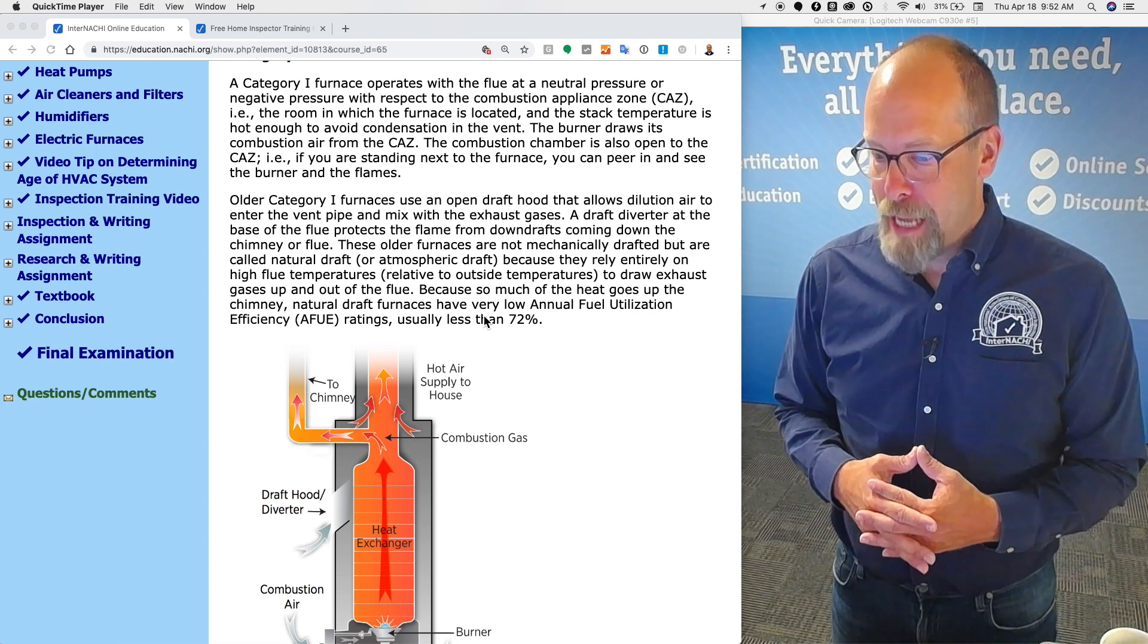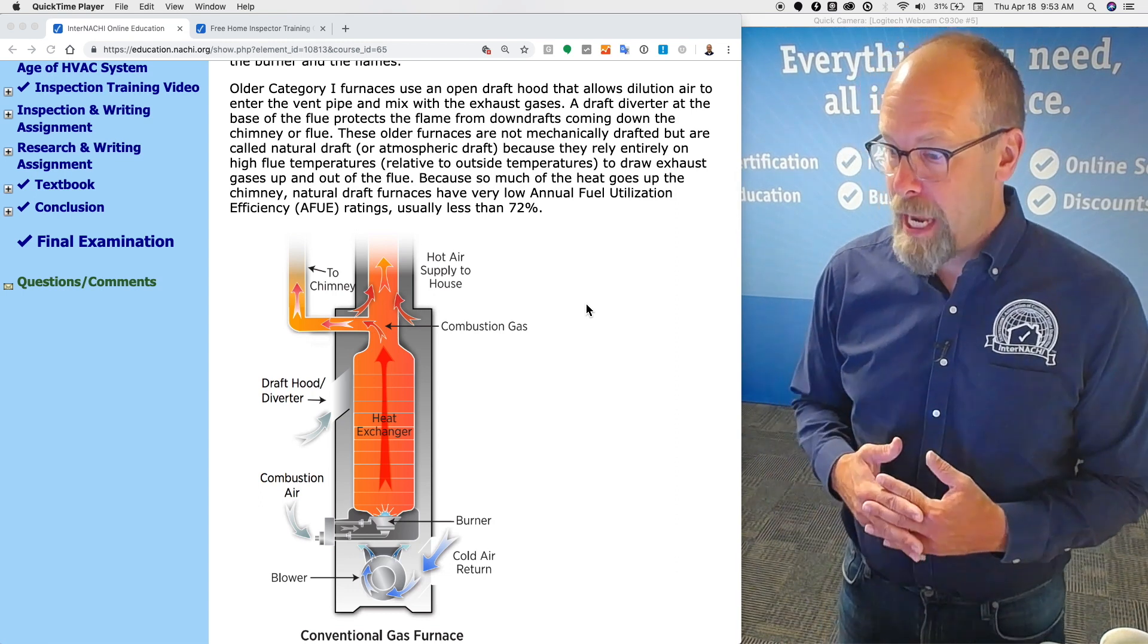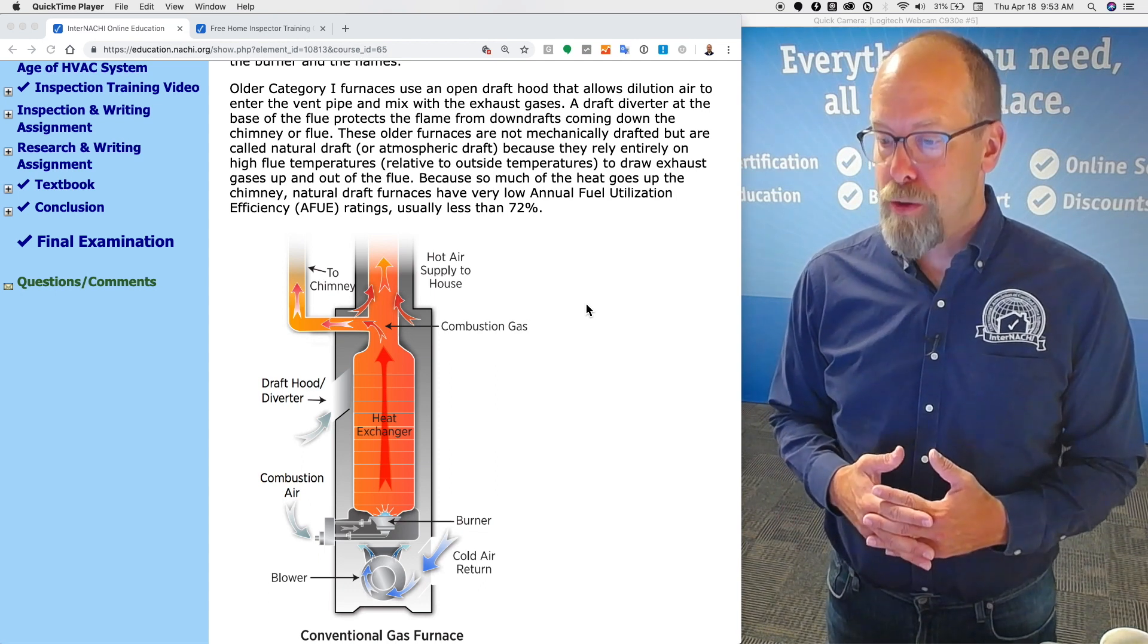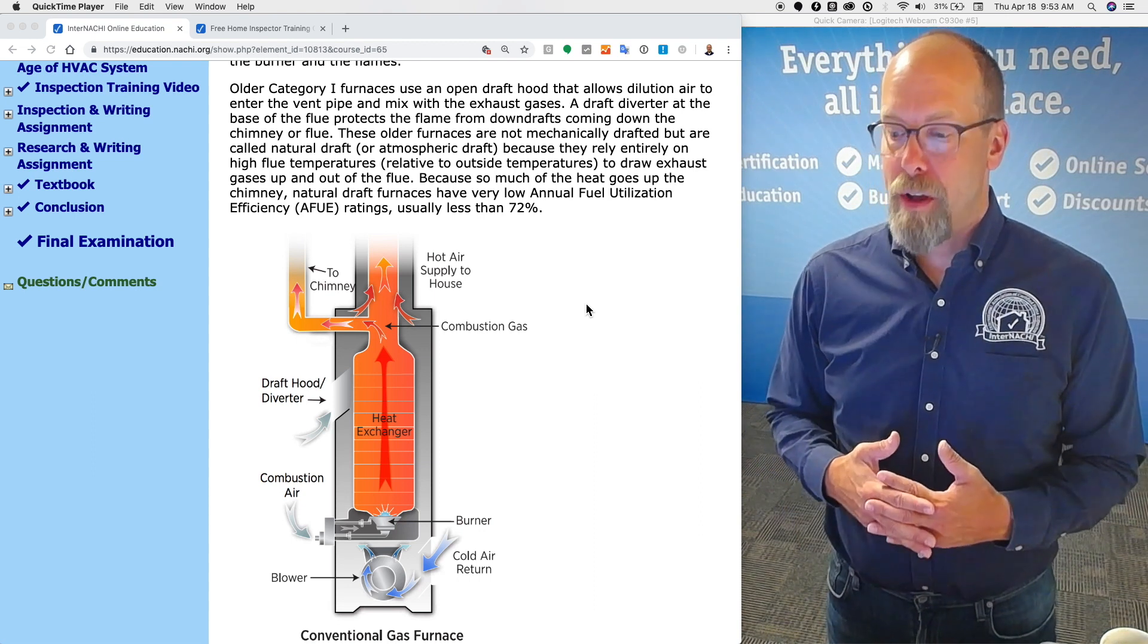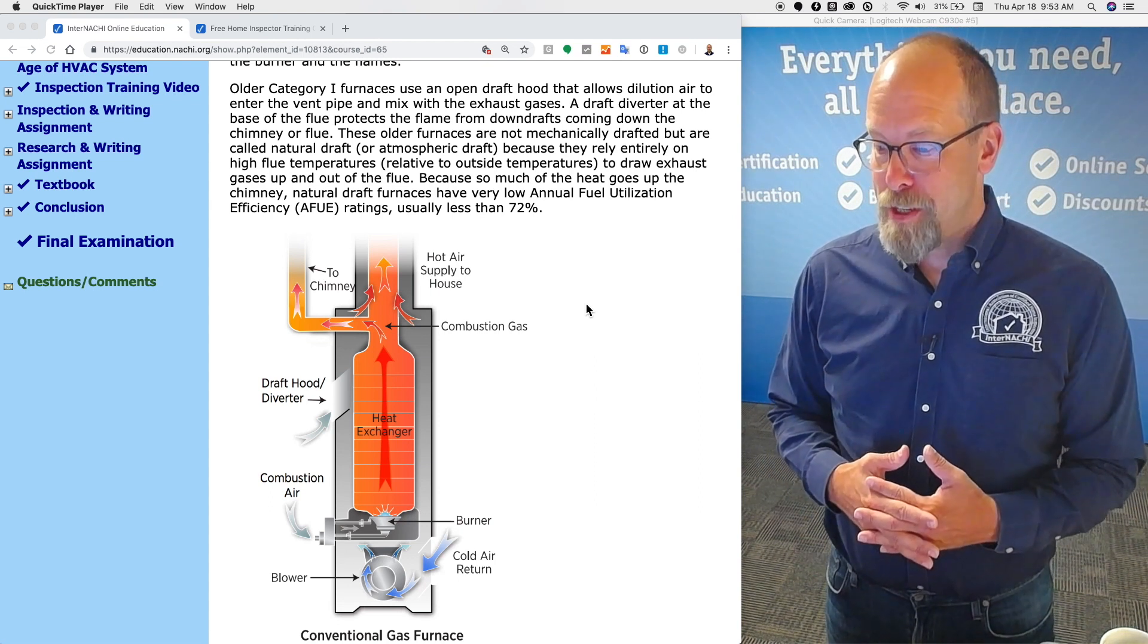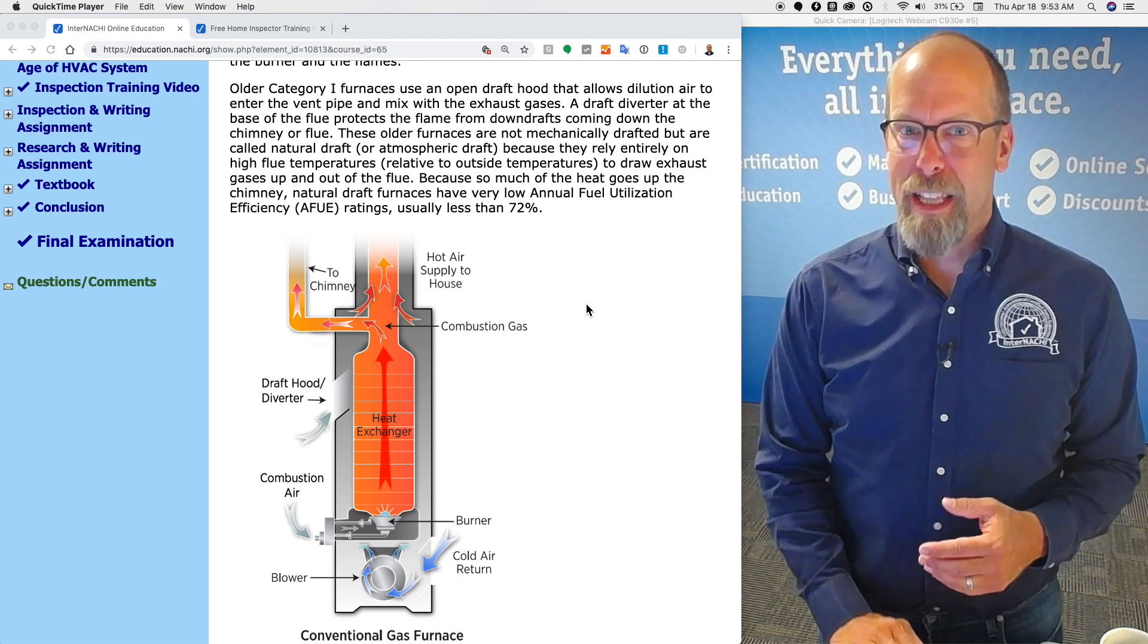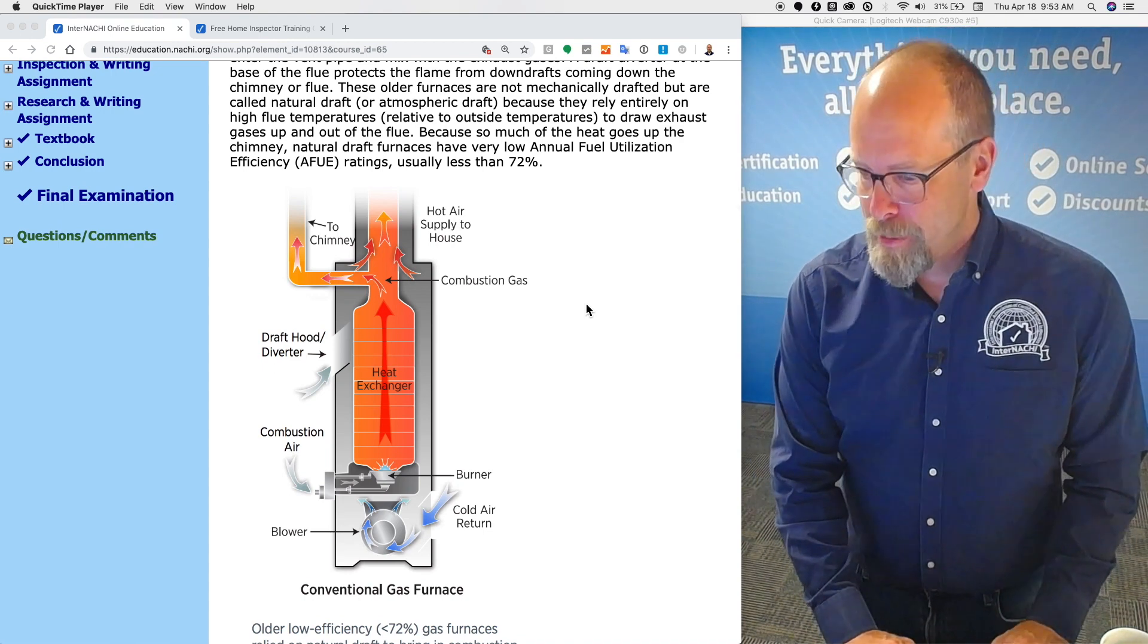A draft diverter at the base of the flue protects the flames from downward drafts coming down the chimney or flue. These older furnaces are not mechanically drafted but are called natural draft or atmospheric draft, because they rely entirely on high flue temperatures relative to the outside temperatures to draw exhaust gases up and out of the flue. Because so much of the heat goes up the chimney, they waste a lot of energy. Natural draft furnaces have very low annual fuel utilization efficiency ratings, the AFUE, usually less than 72 percent. Really low efficiency. They don't make them anymore.